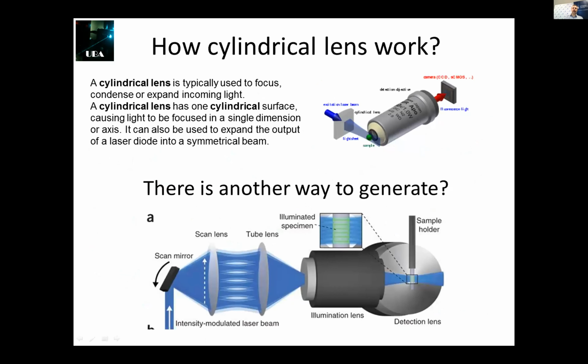But how can we produce the light sheet? Nick already mentioned that we can use a cylindrical lens to produce a flat Gaussian beam, and we can focus this flat Gaussian beam in front of the detection objective, and then we collect with the camera. The other strategy is to use a scanner, a mirror that moves a Gaussian beam across the scanning optics, the scanning lens and the tube lens, and at the end, after it passes through the objective, we produce a light sheet, or a single plane illumination.